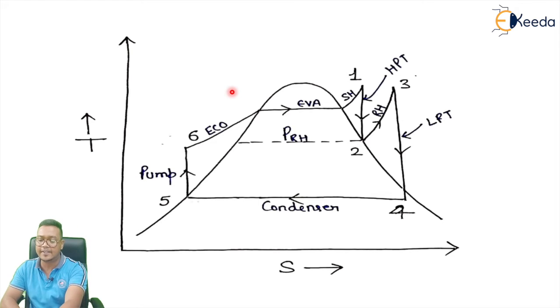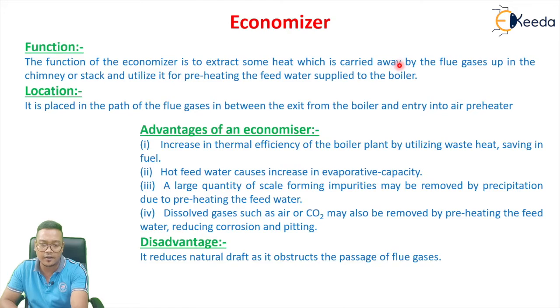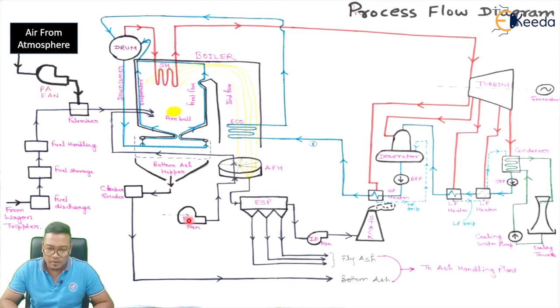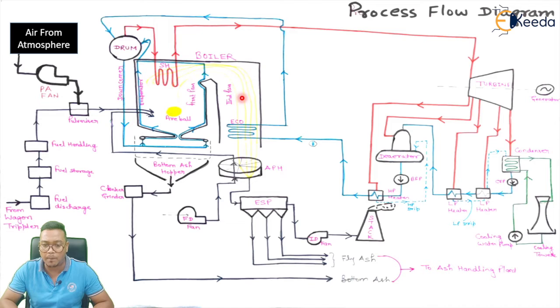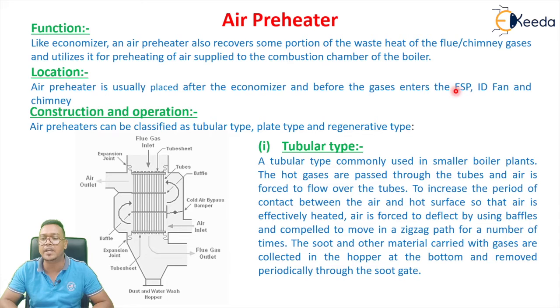Now let's see the next boiler auxiliary — the air preheater. Like the economizer, an air preheater also recovers some portion of the waste heat of the flue gas and utilizes it for preheating the air supplied to the combustion chamber of a boiler. In this diagram, the air preheater takes heat from the flue gas, and this heated air goes into the combustion chamber. The air preheater is usually placed after the economizer and before the gas entering into the ESP, ID fan, and chimney.